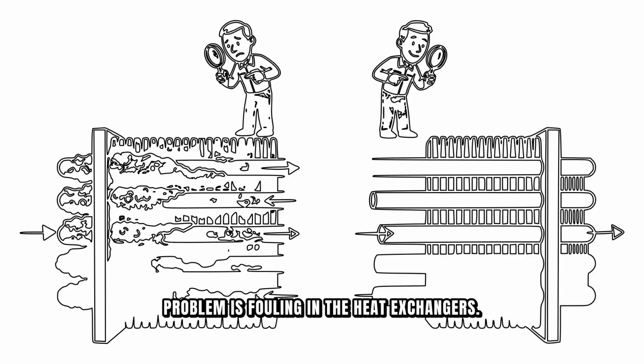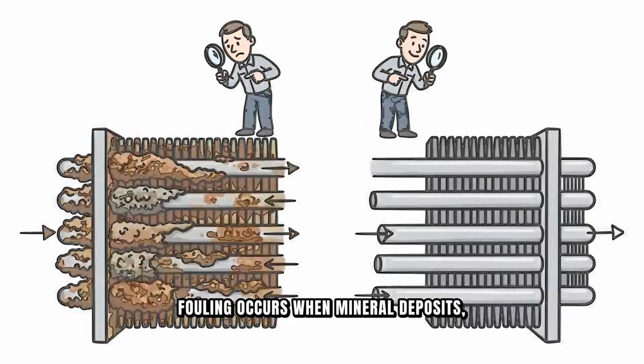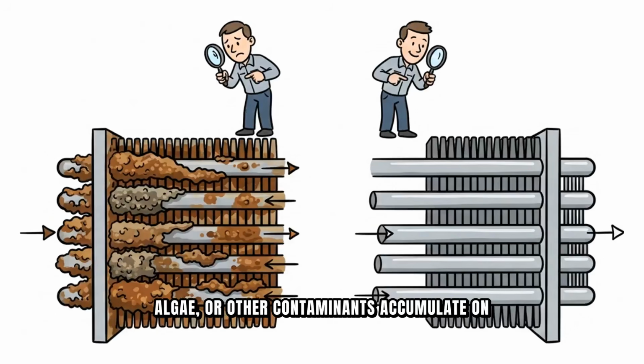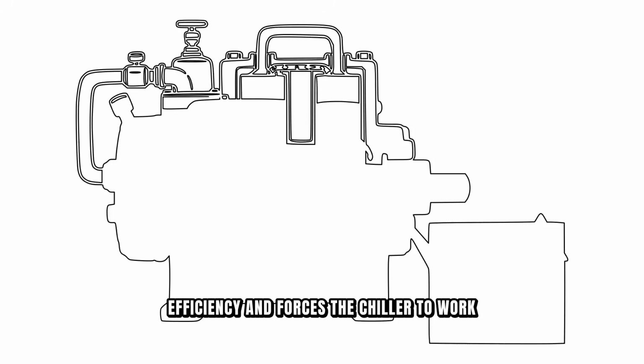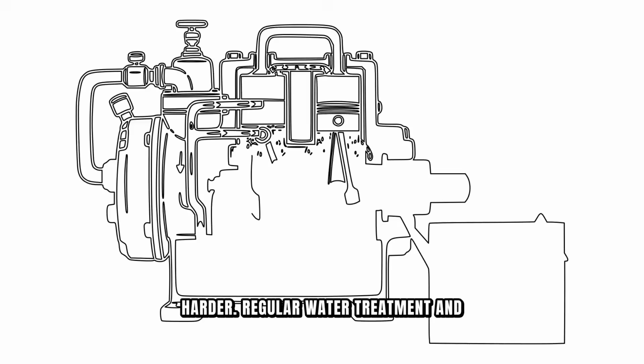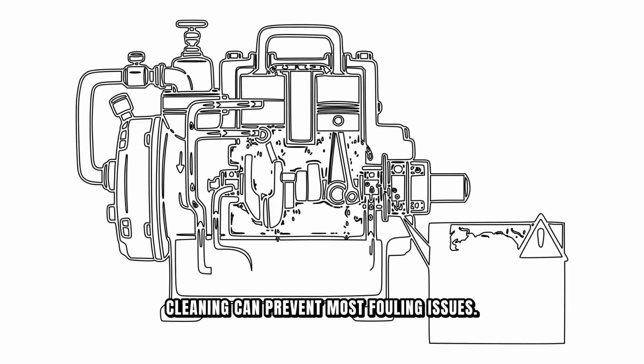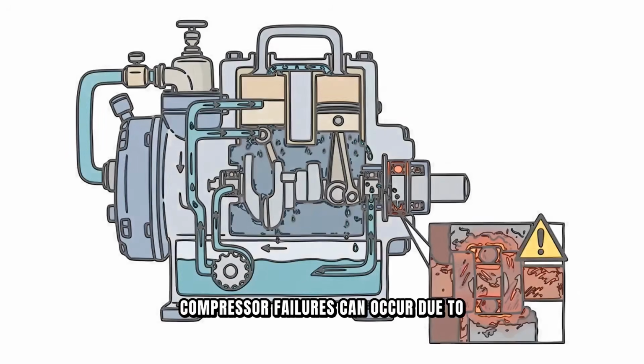Another common problem is fouling in the heat exchangers. Fouling occurs when mineral deposits, algae, or other contaminants accumulate on the surfaces of the evaporator or condenser. This buildup reduces heat transfer efficiency and forces the chiller to work harder. Regular water treatment and cleaning can prevent most fouling issues.